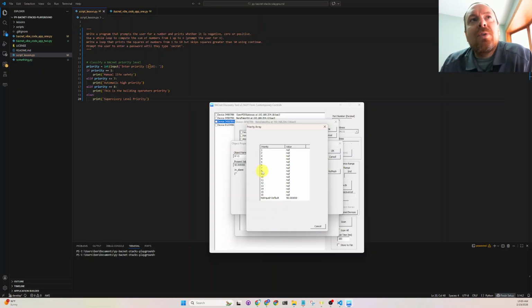And what this was trying to say here is the building operator in building automation, as defined by BACnet, their data comes through at priority 8. So if a building operator was making overrides to a building automation HVAC system through the controls graphical user interface, let's say they're changing a set point or they need to override something because the logic isn't working, it would show up here in the point priority, but anything above this is a higher priority.